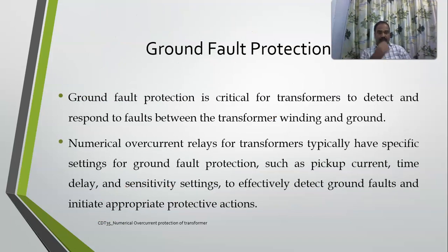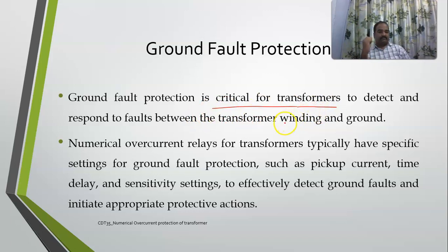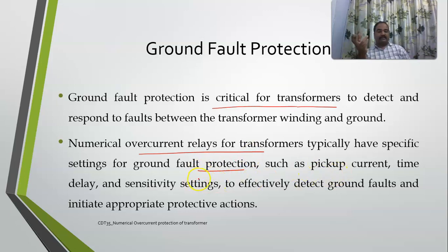The next consideration is ground fault protection. Whenever implementing an overcurrent element, you need to consider whether it should respond to ground faults as well. Ground fault protection is critical for transformers, particularly because phase-to-ground faults are possible in a three-phase system. Numerical overcurrent relays for transformers have separate settings for ground protection, such as pickup currents, time delays, and sensitive thresholds to effectively detect ground faults.